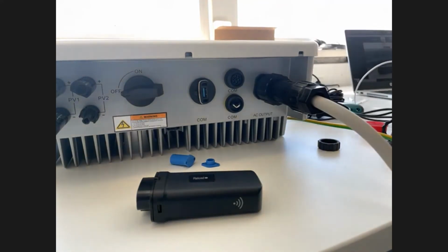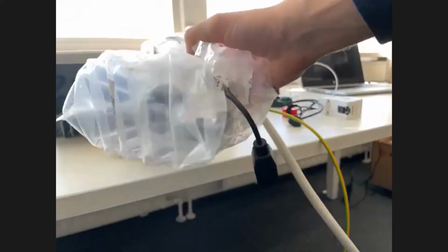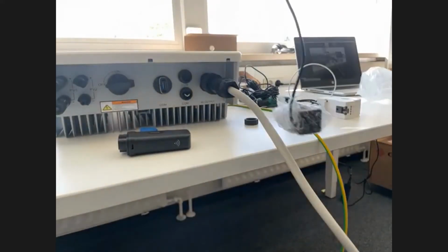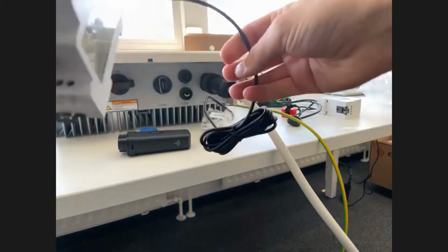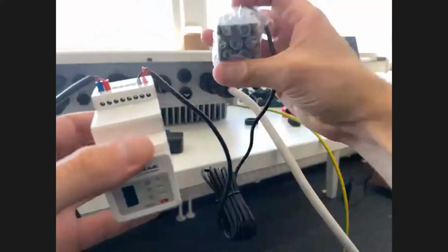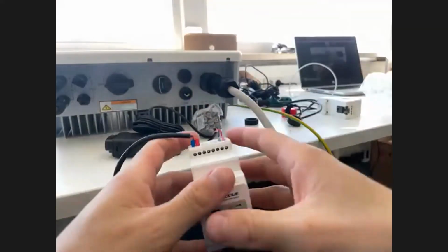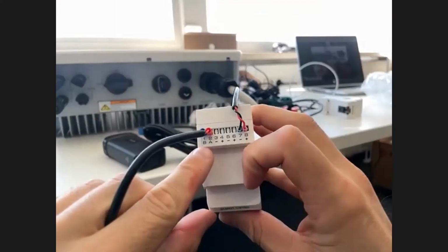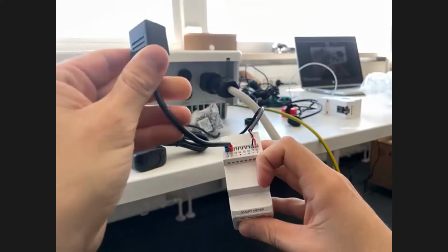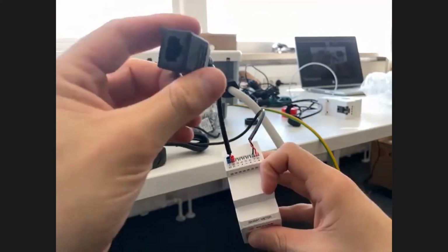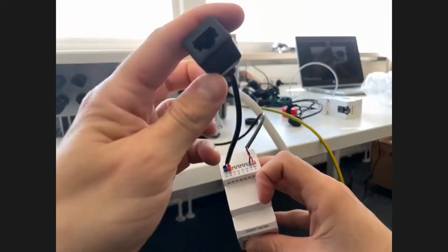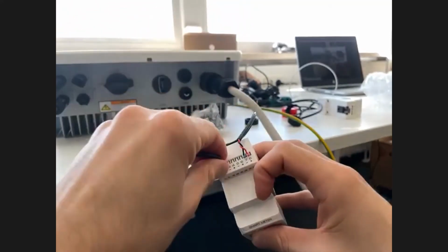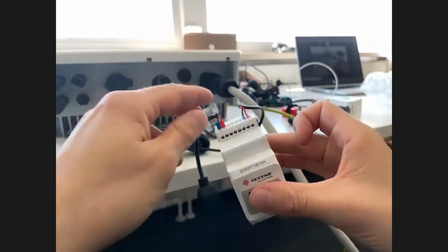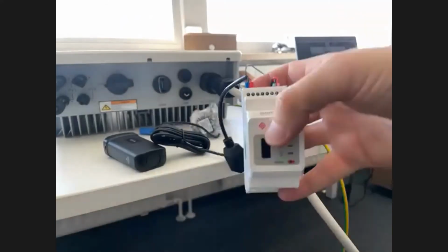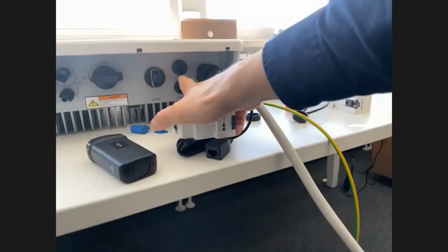And basically, this is how the smart meter looks like when you get it in the package. There are usually 3 CTs. There is only 1 connected now, but usually 3 are connected. And then here on the last 2 pins, as you see, it's already a connected cable. This is because for our hybrid inverters, you use this connector here, but for our grid tie inverters, you need to unscrew those here and then pull out this connector and get some other cables that you can then put into this COM port here.